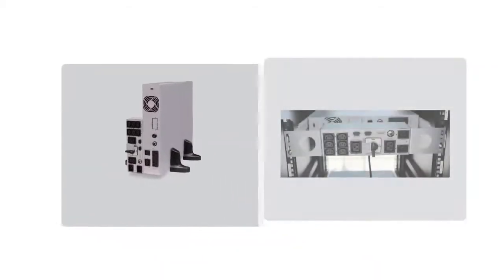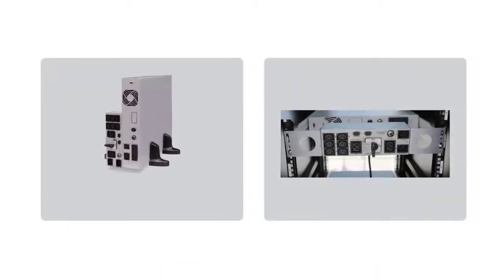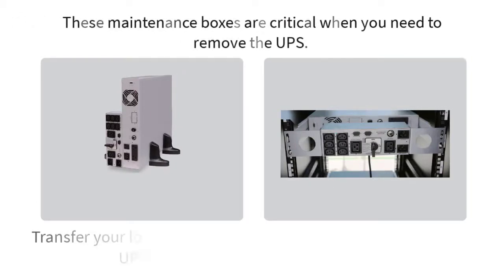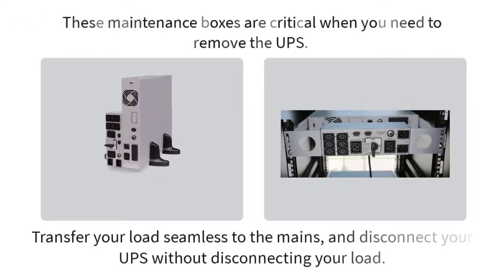You can install an optional maintenance bypass box. This maintenance box can be installed and placed beside the UPS for a tower connection or can be installed behind the UPS with a bracket. These maintenance boxes are critical when you need to remove the UPS. By a click of a switch, you can transfer your load seamlessly to the mains and disconnect your UPS without disconnecting your load.